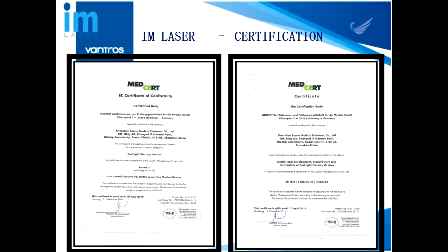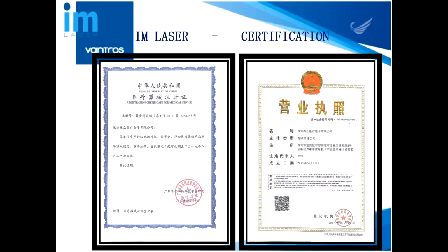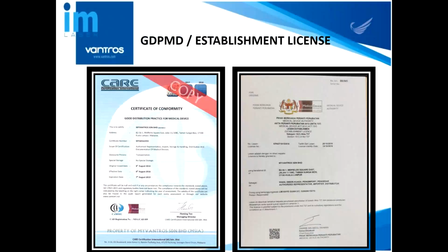Okay, this is the certificate, the ISO 13485 and also the EC certificate of conformity. And in the factory, you also need this certification of a medical device. And in Malaysia, we obtained the medical device cert from our MDA, Medical Device Authority. On the left-hand side, this is the GDP MD I mentioned just now.